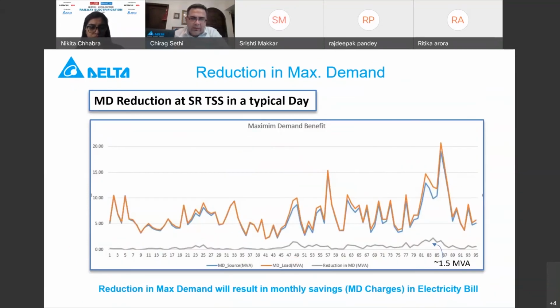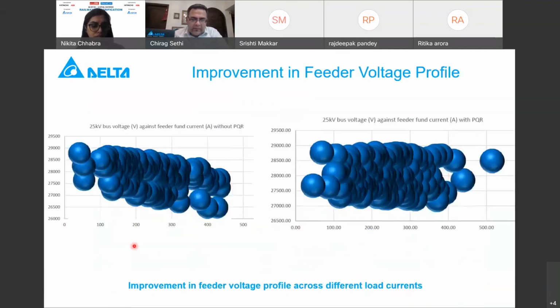As an add-on benefit, we noticed there was also a reduction in the maximum demand for the TSS, which is like a fixed cost to railways. Another benefit we saw is that normally when the load current increases, the 25 kV feeder voltage tends to droop. With our system in place, the 25 kV bus feeder was at a more consistent profile.